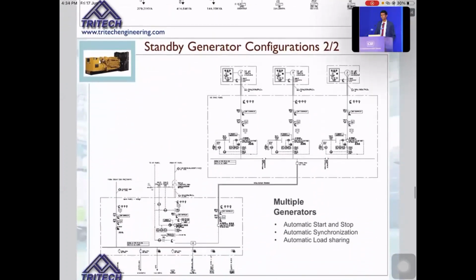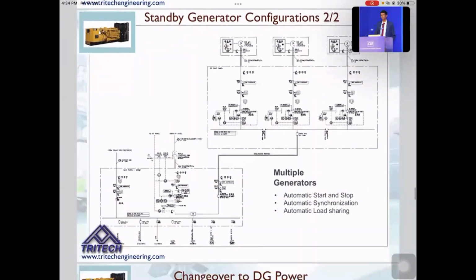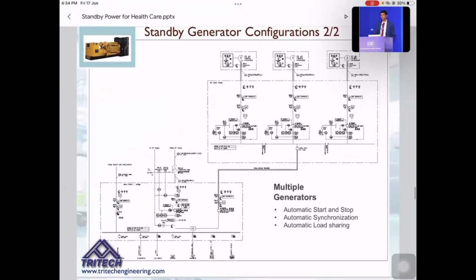So in this case, you have only the automatic start and stop. But in the case of a standby generator with multiple generators, we have this configuration. So there are 3 generators and multiple loads. How they work is, depending on the percentage or fraction of the load that you need at that point of time, only then will the generators come on. So the first one will start and stop, and the second one will start if the load is required, and the third one will start only when the entire load is to be fed. And in the case of loads reducing, they will also switch off automatically. So basically you have automatic start and stop, automatic synchronization, and automatic load sharing. So this is the second system. This is generally for large projects. Again, it saves capital and operating cost when you're planning this fully automated system.